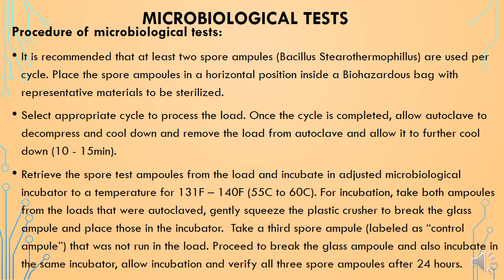Once the cycle is completed, allow the autoclave to decompress and cool down, then remove the load and allow it to further cool down for 10 to 15 minutes. Retrieve the spore test ampoules from the load and incubate in a microbiological incubator at 131–140°F (55–60°C). Take both autoclaved ampoules, gently squeeze the plastic crusher to break the glass ampoules, and place them in the incubator. Take a third spore ampoule labeled as the control ampoule — which was not placed in the autoclave — break the glass ampoule, and also incubate it in the same incubator. Allow incubation and verify all three spore ampoules after 24 hours.